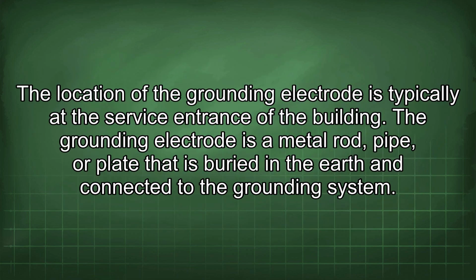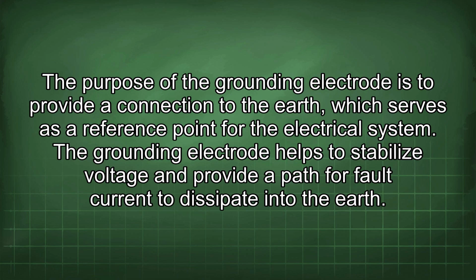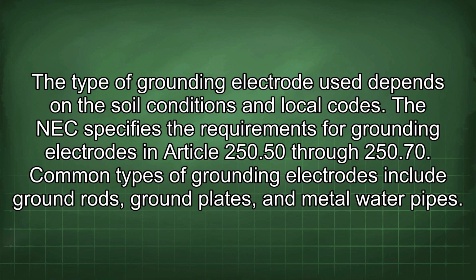The location of the grounding electrode is typically at the service entrance of the building. The grounding electrode is a metal rod, pipe, or plate that is buried in the earth and connected to the grounding system. The purpose of the grounding electrode is to provide a connection to the earth, which serves as a reference point for the electrical system. The grounding electrode helps to stabilize voltage and provide a path for fault current to dissipate into the earth. The type of grounding electrode used depends on the soil conditions and local codes.